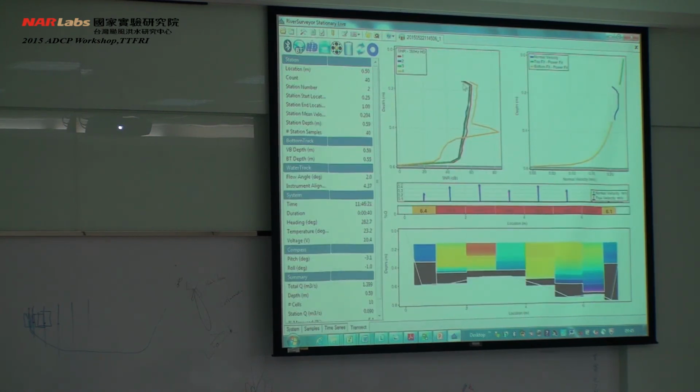10% is the value that they use, as the SNRs have to be within 10% in the test situation in San Diego. So that will have passed that 10%. Ideally, we'd like all of the transducers to have the ceramics that we've got on beam 4, because it's a more efficient ceramic. So that's why you've got that difference.